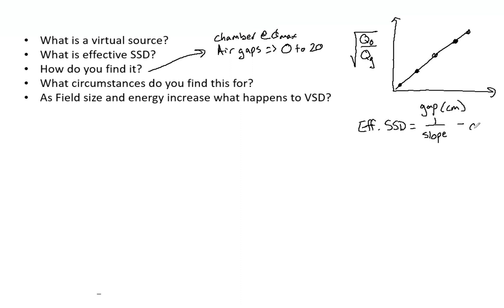So what circumstances do you find this for? When you commission your linear accelerator, you have to do this for every energy, which should clue you into the fact that you also need to do this for every field size.